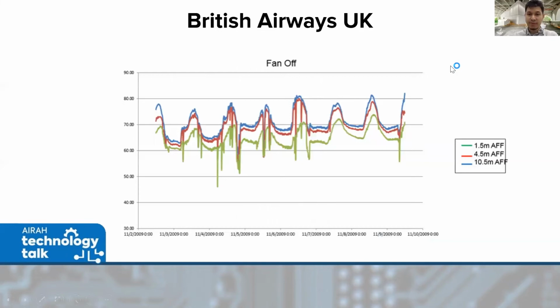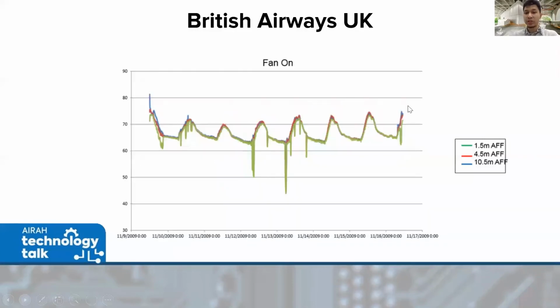This is the data they gave us. Before, with the fan off, shown here in Fahrenheit, there's a massive temperature difference between 1.5 meters at floor level and about 10.5 meters up. When the fan is on, it provides destratification and the temperature levels out - you can see spikes when they open the hangar doors, but otherwise the temperature stays level. That's the benefit of destratification.